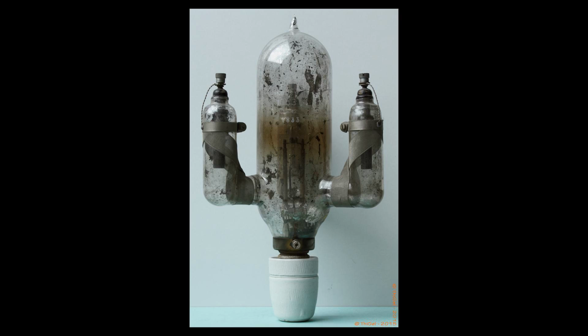However, the tall porcelain column required to house the grading electrodes was more difficult to cool than the steel tank at cathode potential, so the usable current rating was limited to about 200 to 300 A per anode. Mercury-arc valves for HVDC were, therefore, often constructed with 4 or 6 anode columns in parallel. The anode columns were always air-cooled, with the cathode tanks either water-cooled or air-cooled.